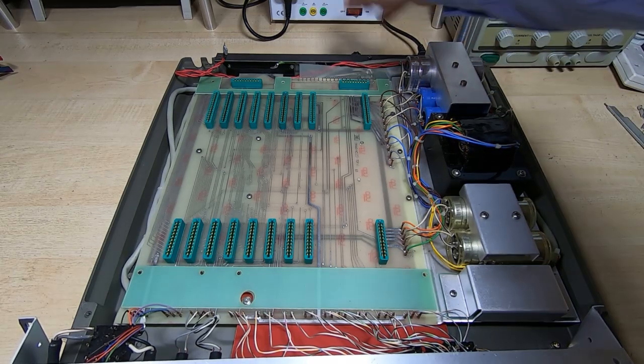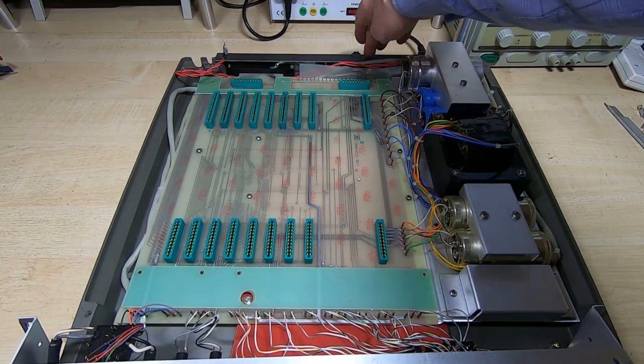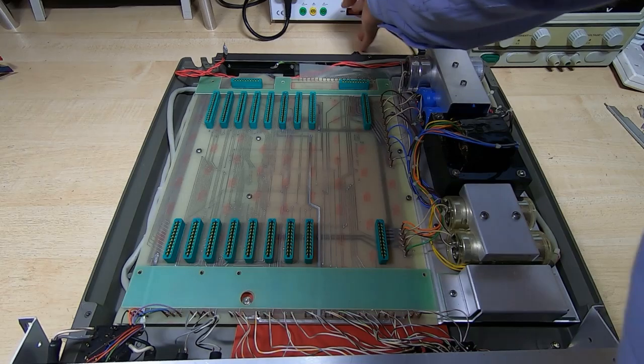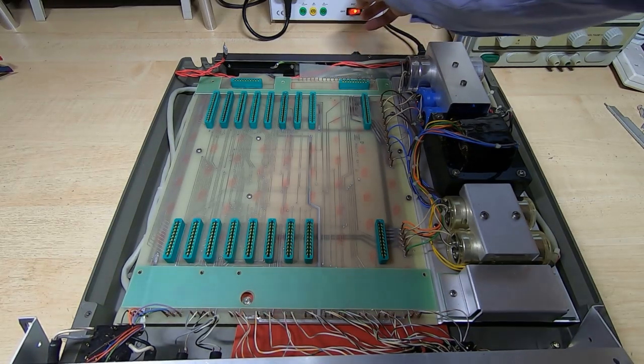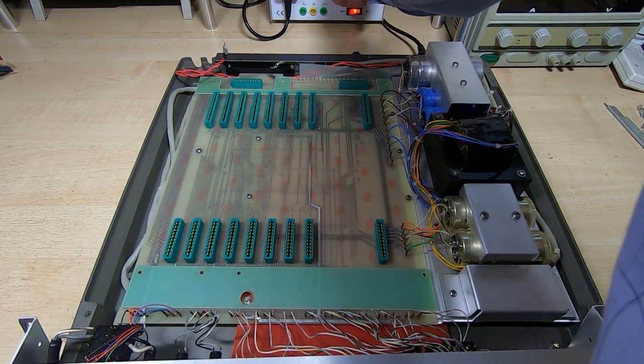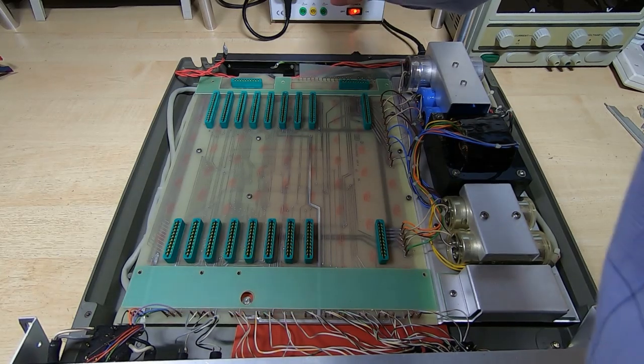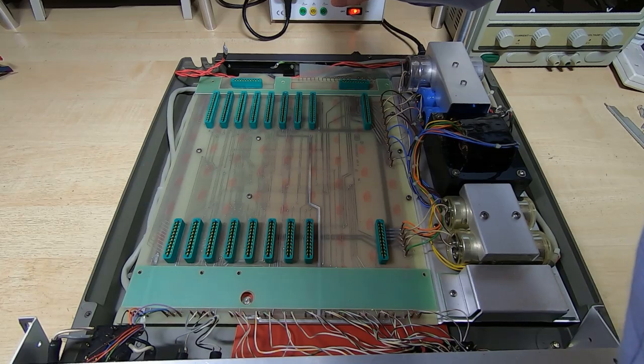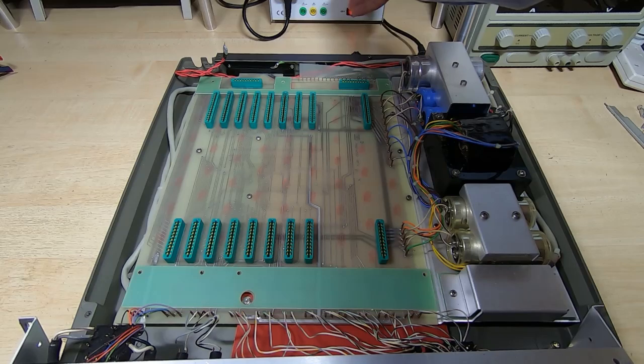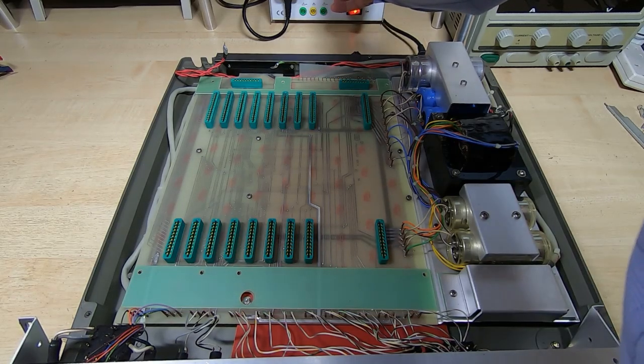So we'll power it up. I've checked to make sure it's set to 230 volts, so that's fine. Power this up, and I'll run it up to about 150 volts. I'm not going to take it all the way up to 240 simply because without a load on it, it could cause the transformer to overheat.